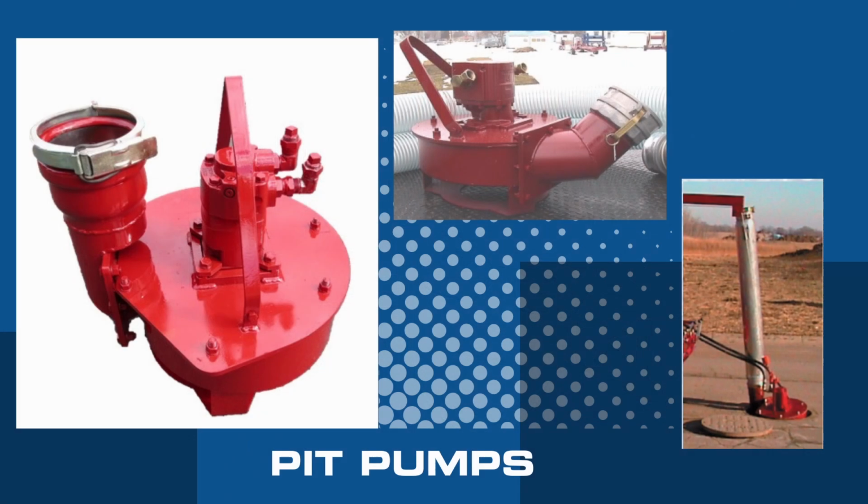Now, another way to dewater an area is also a pit pump. They can be submerged into a manhole. They can be handled manually. They weigh less than 200 pounds. They only need to be primed from 1 to 2 feet, so you don't need a lot of water for it to be under before it starts pumping and doing its thing. The hydraulic supply is the power supply, so you can technically connect this pump to a hydraulic system, as long as it has enough power that you already have in your yard. And we're talking decent numbers here. 1,200 GPM can be pumped through 660 feet of hose, and you can possibly use it in conjunction with a hose reel.